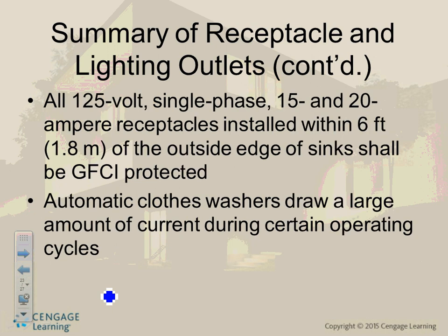GFCI, the following: anything within 6 feet of a sink, guys, has to be GFCI. Any sink, if you have a receptacle within 6 feet of the kitchen sink, the bathroom sink, the laundry sink, and the bar sink that you have in your basement, Patrick. Any receptacle, 15 and 20, has to be GFCI. Okay, where else do I need GFCI? Bathroom receptacle, GFCI. Laundry area, GFCI. Outdoor receptacle, GFCI. Unfinished basement, GFCI. How about garage? Garage receptacle, GFCI. How about the kitchen countertop? All the receptacles on the countertop.